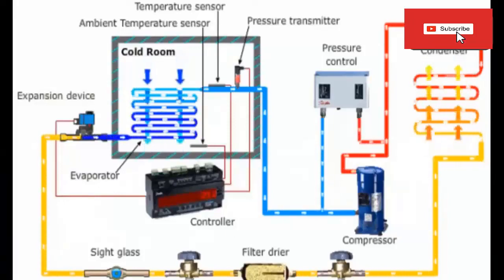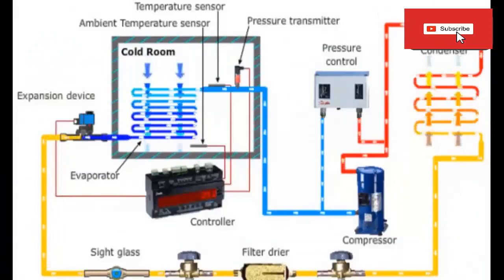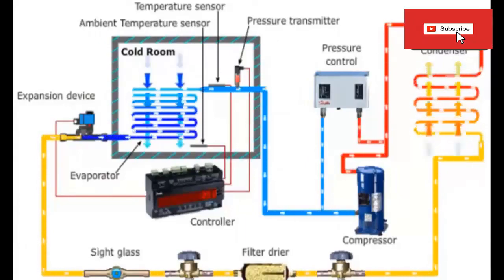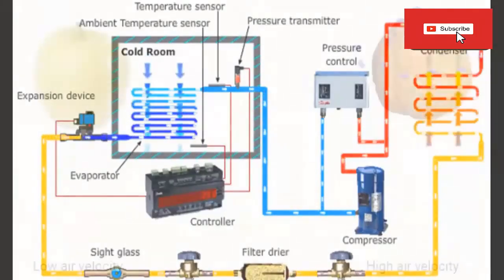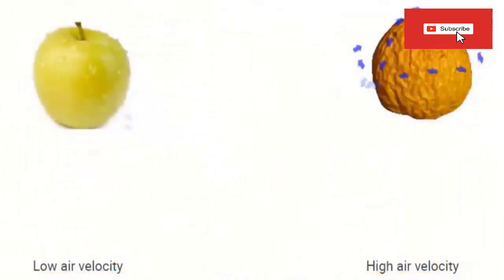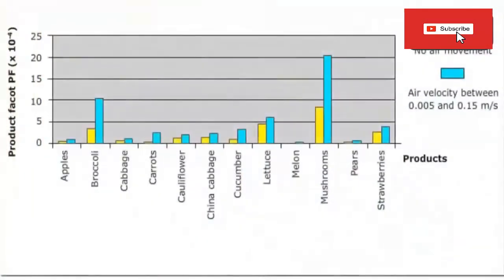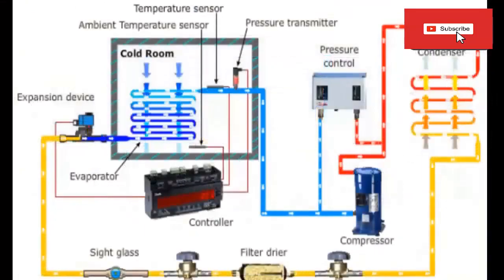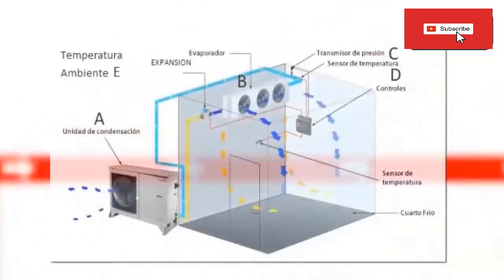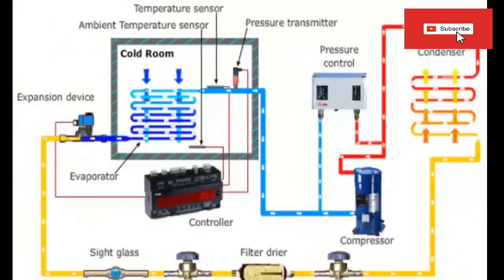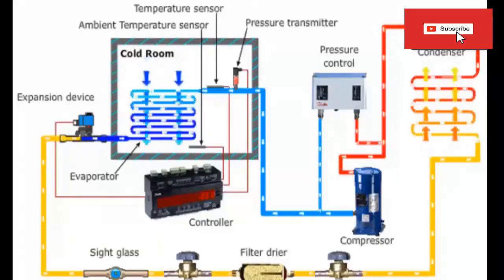Air speed: To understand the control of air speed in a cold room, we are going to analyze the following aspects. A. The cold room controls the speed of the air to avoid dehumidification. B. The high speed of the air increases the coefficients of convection and heat transfer. C. The speed of the air influences the cooling and dehydration of the product. D. Higher air flow velocity increases product heat transfer and dehumidification rate. E. The increase in the rate of dehumidification of the air causes the loss of the water content of the product.